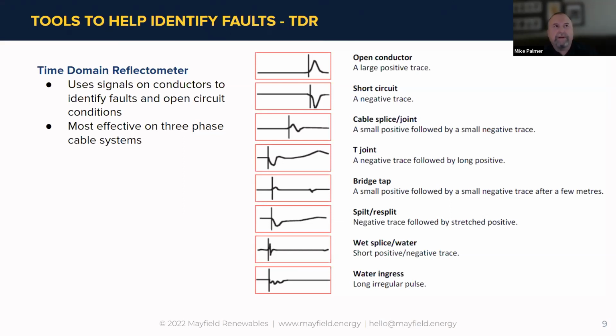Typically, when we see water get into a cable, a power cable, whatever kind of cable it is, telecom, whatever, you don't dry them out anymore. You typically find the wet spot from both directions, and you dig it up and replace that wet section of the whole cable. But in PV, and I mentioned the DC side, where we have USE-2 type cables, as we all know, there's only one conductor. They're usually direct buried. They're not in conduit. So we have other means at Megger to find those faults.